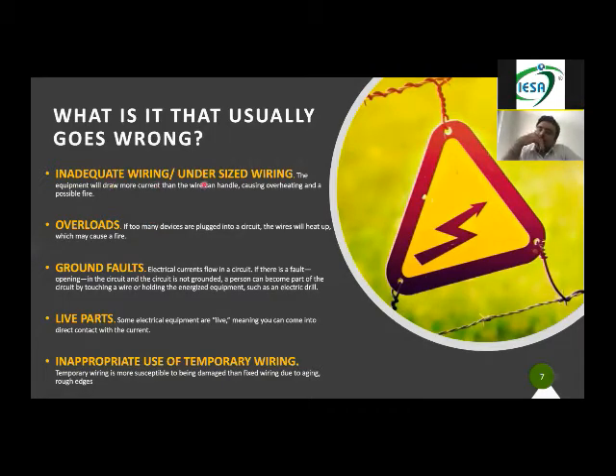Inadequate wiring, undersized wiring. When I say inadequate or undersized, there is a certain capacity of the genset if you're taking power. There is a certain capacity of the house power if you're taking power from the house. And if you're putting undersized cables, not as per the load which is being given, ultimately what will happen? It will heat up, they get melted, and it will result in fire.